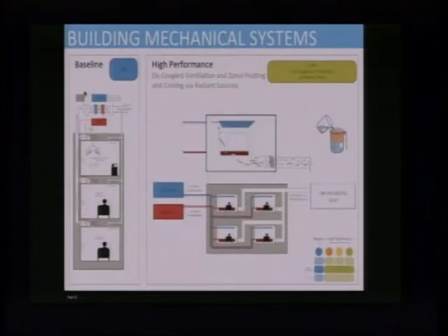So for the high performance models, as I talked about, we're decoupling the thermal tempering from the ventilation air. We're doing that through displacement ventilation with radiant cooling and heating. I should say that this is mostly in the patient rooms, and really in 80% of the model, we're using that kind of system. In places like the OR, the ED, the kitchen, we're using a really high performance version of VAV still. It doesn't make sense to decouple in those areas. The requirement for air change rates is just too high. And so we used overhead mixing systems in those more highly regulated spaces with the ability to massively turn down at night when they're not being used. We'll see that in the data where the turn down is, and you can actually see the difference in energy use.